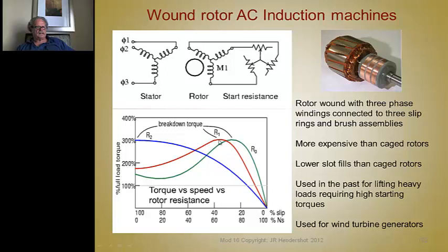Now the red one has a higher resistance rotor, so it's got high starting torque, but the slope is also more, so the slip is higher. If this is your torque value you're after, that's the slip for this rotor, that's the slip for that rotor, and a whole lot of slip to get that much torque out of a rotor that has high resistance is putting out a very high starting torque.